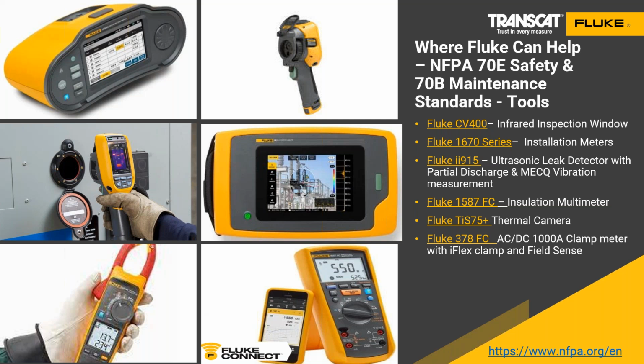Running a piece of equipment that allows me to see that future failure before it happens. The idea is simple: you can't fix what you can't measure, but if I can measure it, I can determine its overall health and where it is in its lifespan. Now I can make qualified judgments to pull and replace before we hit breakdown, and take things down in an orderly fashion where I can plan for the outage and pull that motor or transformer at the appropriate time.